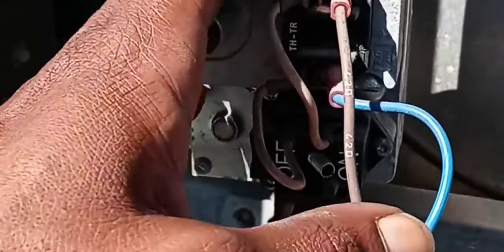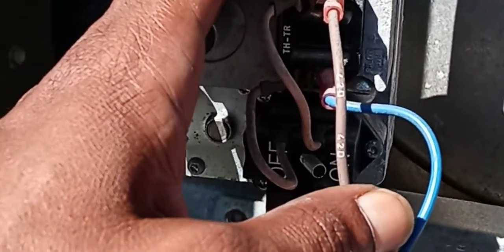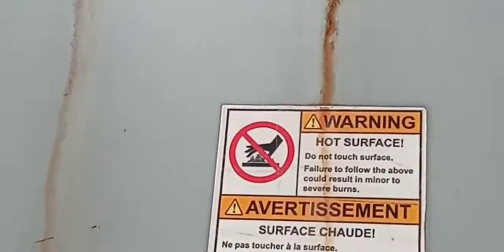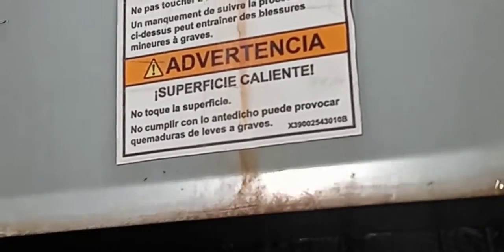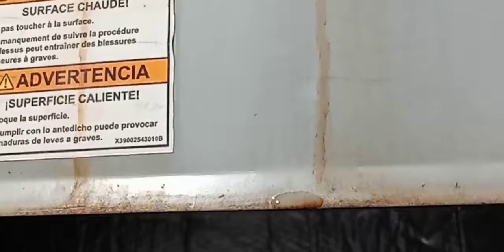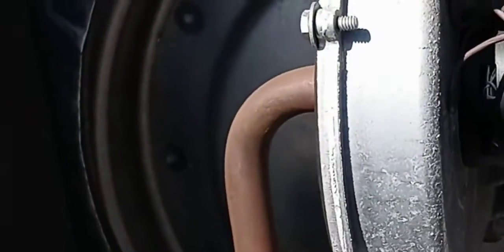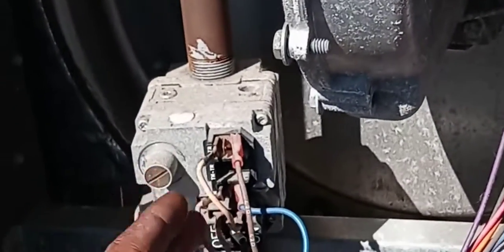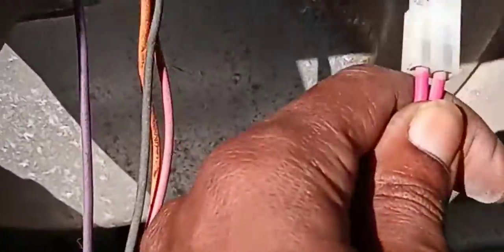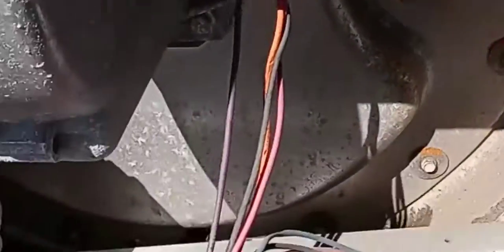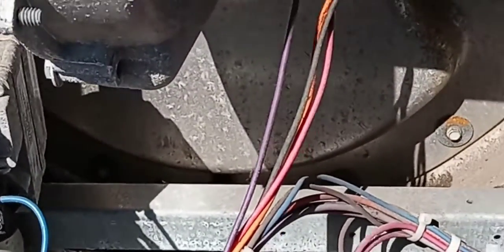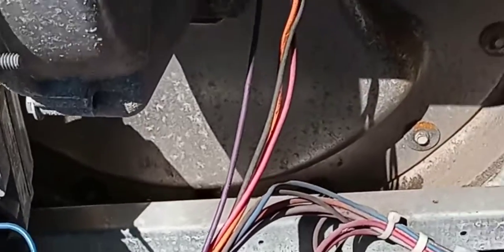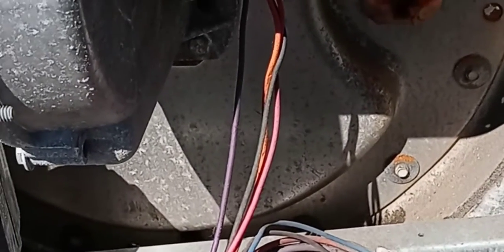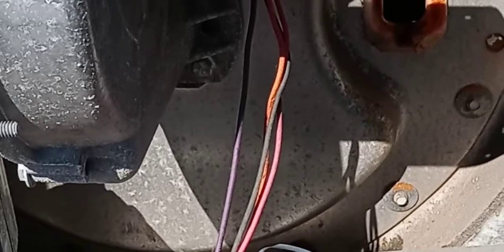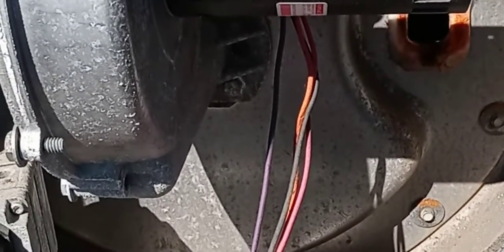Well, first I knew it was working because you could smell the gas coming out. Before it fires up, you could smell pilot gas being let out. So I smelled that. And then I actually tested and made sure I had 24 volts come in here. I took this thing off. This guy plugs into my hot surface igniter. I verified that I had 120 volts there, plugged it back up, tried it again. The unit coughed again. Heat comes on for about 10 seconds. So I know my gas valve is working. I know my inducer's working.